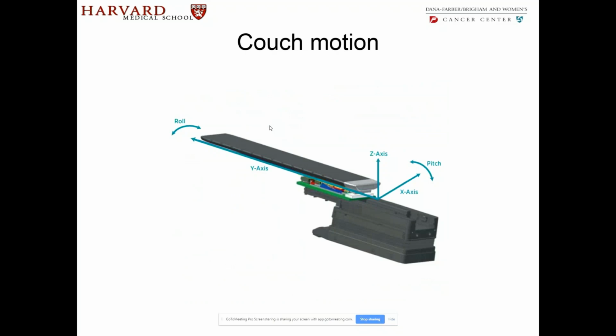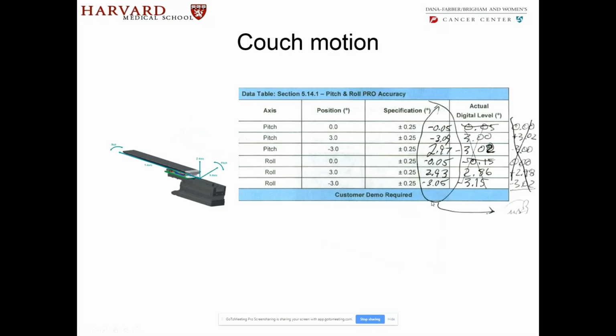In the case, now we come to the couch also has tolerances. This couch actually has a roll, and it can tilt up and down, which is the pitch. And then, of course, it has the XYZ axis along which it can move forwards, backwards, to the left, up and down, left and right. And we had an interesting situation here. The situation was that when they brought this couch in and they said, okay, we have our test, we'll run our test, and you can see what the position of pitch and roll should be here. The position is in degrees. Pitch, 0 degrees, plus or minus 0.25 degrees is their tolerance.